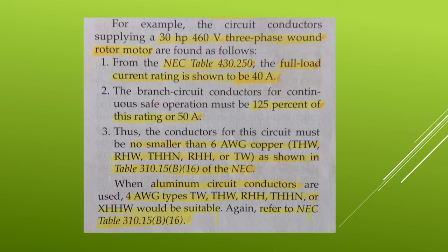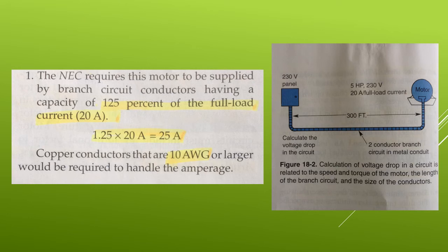When aluminum circuit conductors are used, 4 AWG types TW, THW, RHH, THHN, or XHHW would be suitable. Again, refer to NEC table 310.15(B)(16). Voltage drop. Voltage drop, as you can recall, is the reduction in voltage along the length of a conductor. This is important to know when you have to wire a circuit for a motor, because voltage drop greatly affects the speed and torque of a motor.